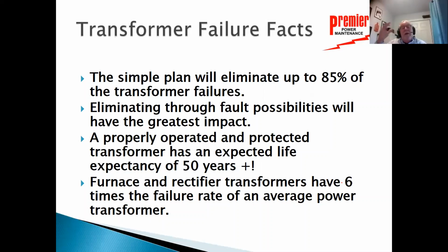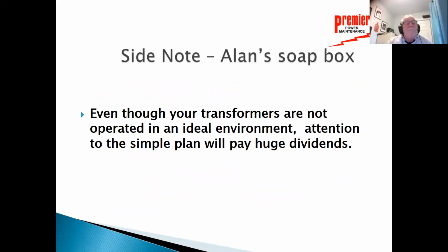If you get rid of that fault possibility, or reduce that, that would have the greatest impact that you could possibly have. Operating that system as we've indicated, with the preventive maintenance system, the life expectancy of that transformer should be at least 50 years. Now, if you're working with customers that have furnace transformers and rectifier transformers, they have 6 times the failure rate. They're not operated on an ideal basis.